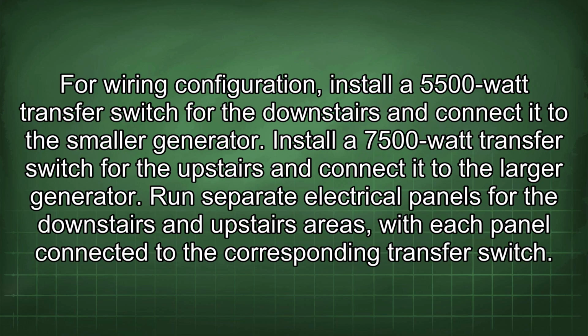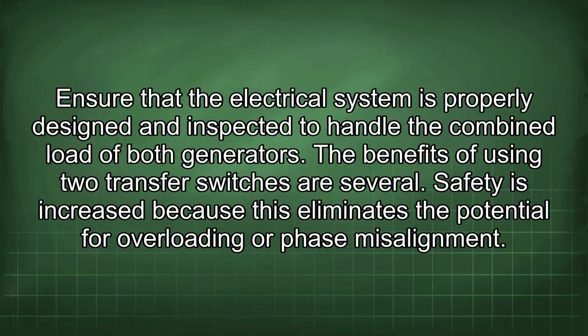For wiring configuration, install a 5500 watt transfer switch for the downstairs and connect it to the smaller generator. Install a 7500 watt transfer switch for the upstairs and connect it to the larger generator. Run separate electrical panels for the downstairs and upstairs areas, with each panel connected to the corresponding transfer switch. Ensure that the electrical system is properly designed and inspected to handle the combined load of both generators.